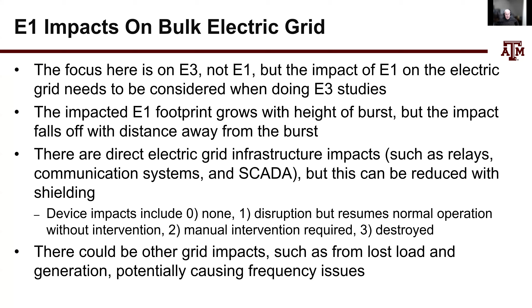The E3 impacts are caused by the nuclear weapon's explosion perturbing the Earth's magnetic field, similar to what's caused by a geomagnetic disturbance. When you assess these, you look at how fast the Earth's magnetic field changes with time, expressed as dB/dt, usually in nanoteslas per minute. A nanotesla variation in the Earth's magnetic field is like moving a magnet around a conducting sphere, which induces a voltage. How much voltage gets induced depends on how strong that magnetic field is and how rapidly it's changing.